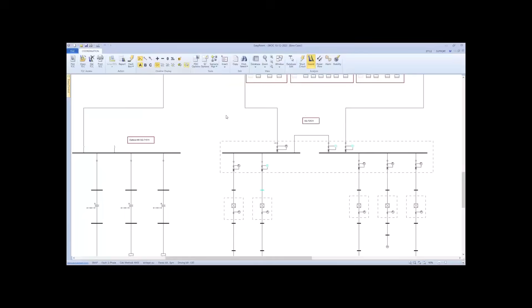I had to select this, and I see how - if I have a fault here - I see how the current goes, passing through this relay, this breaker, because this incoming is open, and goes up to here, finishing on the gas turbine. So we see that all our relays are green, meaning the sequence of events is correct.